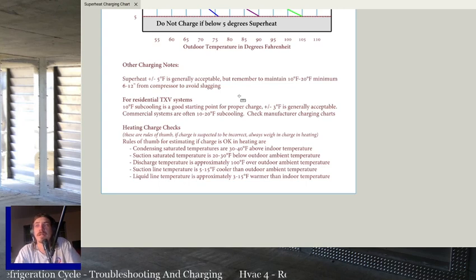Discharge temperature is approximately 100 degrees over outdoor ambient. That's the only one that you can't go by what is normal to figure it out, but it's basically just saying you're picking up heat and you should be close to what you're trying to get inside. Systems that work better in low ambient, your mini splits and stuff like that, may even be over this. Your green speed systems may even be over this, but your discharge temp is what hits your indoor unit, right? So you need to have a reasonable amount of heat to be able to give off that heat in the condenser.